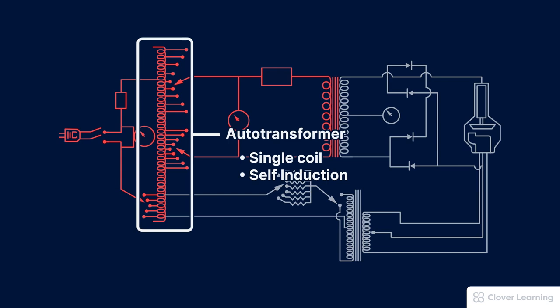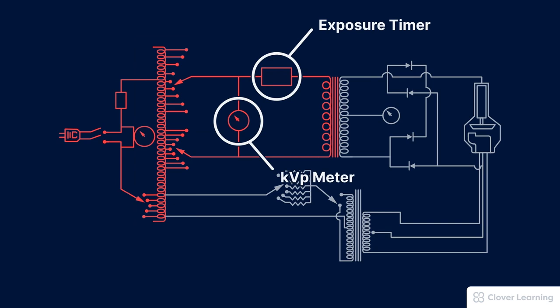There are two components that follow the auto transformer: the kVP meter and the exposure timer. The electricity on the primary side of the circuit is still in volts and not kilovolts. But there's a reason that we place the kVP meter here. It's pretty simple. Volts are easier to measure and the reading can be easily converted to kilovolts.